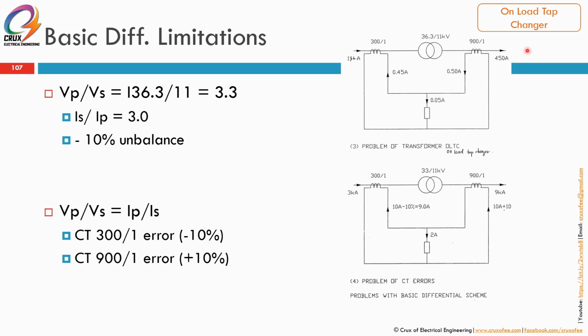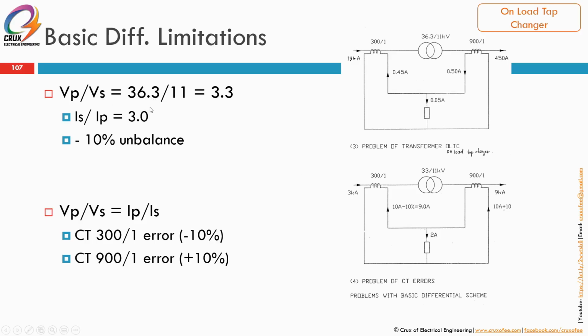Problem number 2, on-load tap changer. You use an OLTC transformer. When using OLTC, it actually changes the winding turns of the transformer. So the CT may be the same 300 to 900, 33/11. Let me correct a little, there is a mistake: VP over VS. The VP over VS ratio we can see here is 36.3 over 11, that is 3.3, but IS over IP, the secondary 900 over 300, gives 3. So your reading should be correct, but there is some unbalance, a 10% unbalance, because the secondary reads a bit lower because of the turns ratio issue.